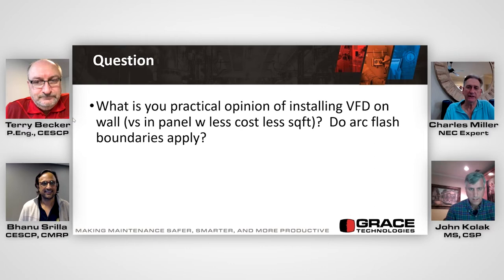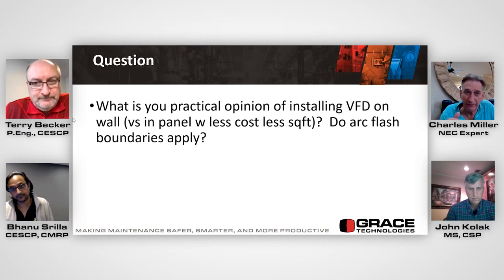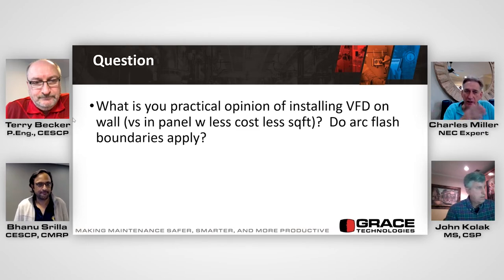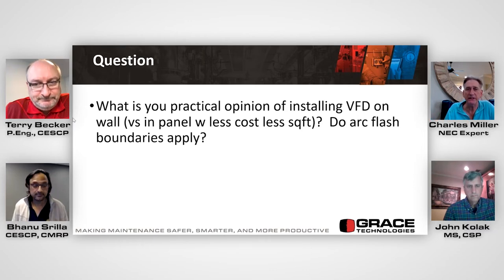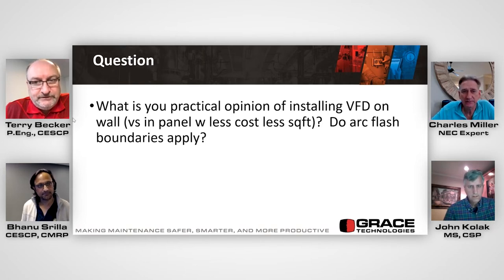I agree with him. I think as long as the VFD is finger safe, touch safe, but I also know Terry is exactly right when he said it has to be in normal operating condition, all the covers have to be on. One thing that quite often happens with VFDs is the little covers over the incoming and outgoing power get taken off and left off. At that point, it's no longer finger safe and touch safe. But as Terry said, I agree that in that case, that's not normal operating condition because the covers are not on there. Correct.